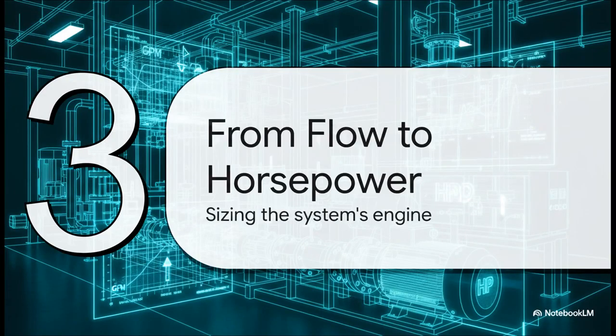All right, so check this out. We now have the two critical pieces of our puzzle. We know how much water to move, that's our GPM, and we know how hard we need to push it, that's our head. With just those two values, we can finally figure out just how powerful our pump's motor needs to be. We can calculate the horsepower.